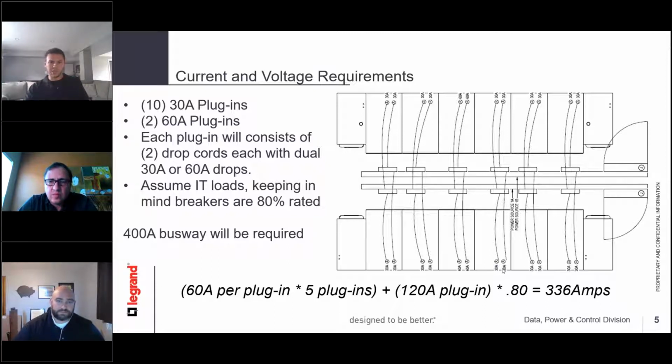So what you're saying, Corey, and I've come across this quite often too, is we'll get the power rating of this cabinet right here. We'll have the kW of this, but what we're really after is the amperage of it, right? We need to know from the plug-in level what the connector is going to be. Typically, you're seeing IEC connectors, correct? Correct. For most of the data center industry, we would see either 5-pin 30 amp IEC connectors, and still a lot of L630 NEMA connections. Okay, so that's what's important on these.